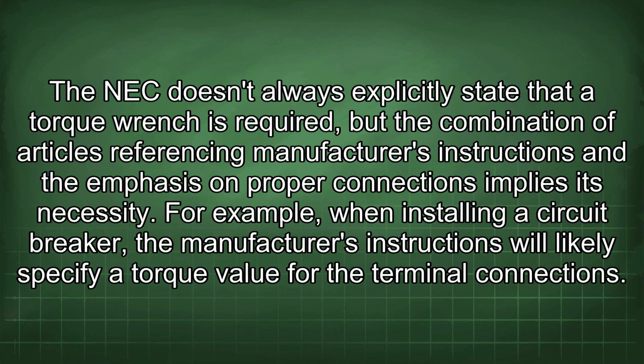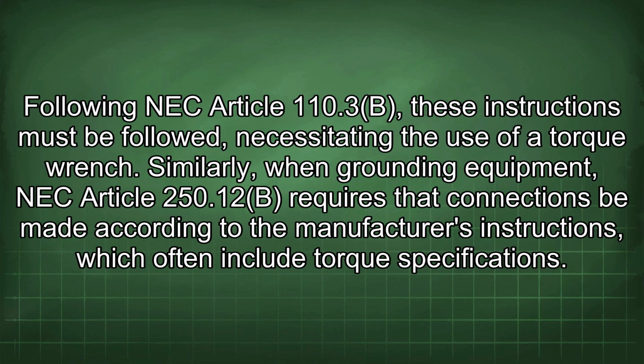The NEC doesn't always explicitly state that a torque wrench is required, but the combination of articles referencing manufacturers' instructions and the emphasis on proper connections implies its necessity. For example, when installing a circuit breaker, the manufacturer's instructions will likely specify a torque value for the terminal connections. Following NEC Article 110.3(B), these instructions must be followed, necessitating the use of a torque wrench.